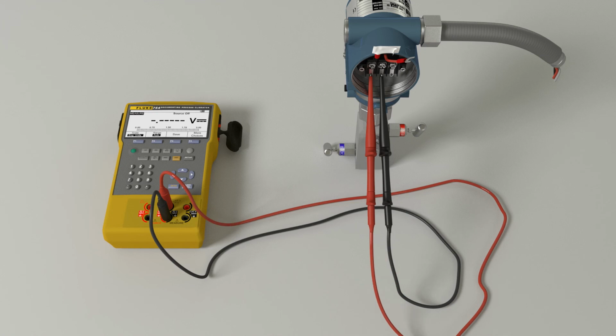We are ready to configure the meter for calibration now. If you are at this point, you should have isolated the manifold, you should have connected your hand pump, and you should have connected your pressure module.